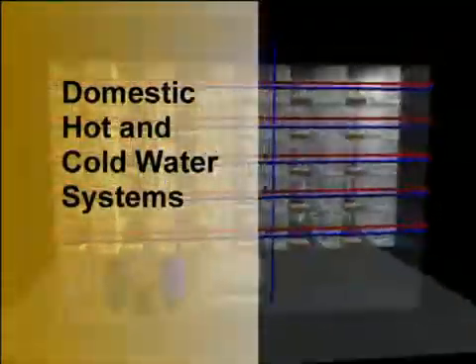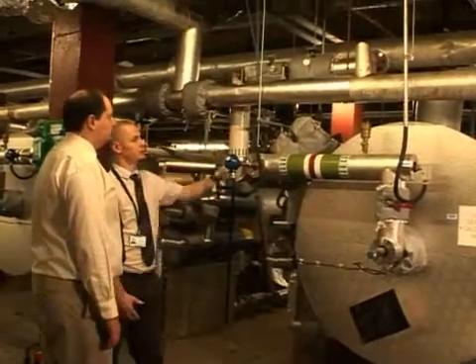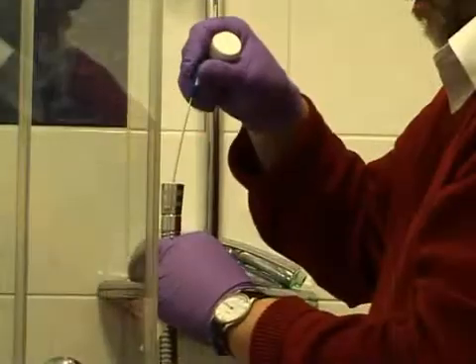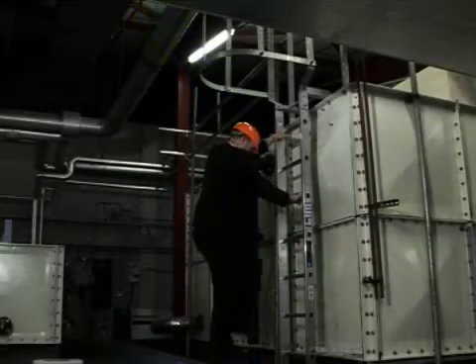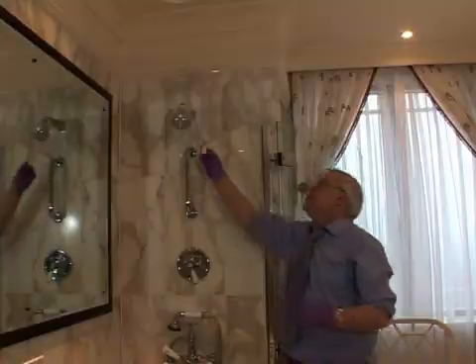Domestic hot and cold water systems are a potential cause of outbreaks. The larger and more complex the water distribution system is, like in hospitals and hotels, the more prone they are to colonisation. But systems in private homes can be a source of infection too. When monitoring or investigating hot and cold water systems, it is essential to measure water temperature. Examine the system from where water enters the building, working through the intermediate stages of tanks, water softeners, and water heaters to the points of use.